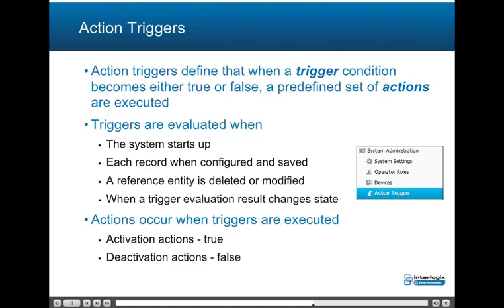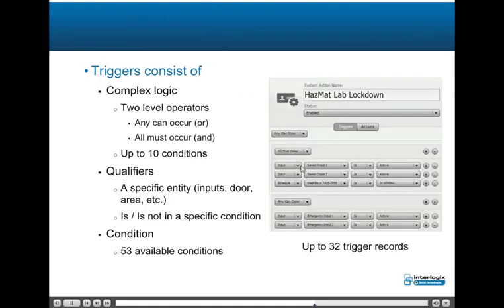Action triggers define that when a trigger condition becomes either true or false, a predefined set of actions are executed. Triggers are evaluated when the system starts up, each record is configured and saved, a reference entity is deleted or modified, or when a trigger evaluation result changes state. Actions occur when triggers are executed: activation actions (true) and deactivation actions (false). Triggers consist of complex logic with two-level operators: any can occur or all must occur, with a maximum of up to 10 conditions. Qualifiers include a specific entity such as an input, door, area, etc., configured as 'is' or 'is not' in a specific condition. There are 53 available conditions, and the system supports up to 32 trigger records.